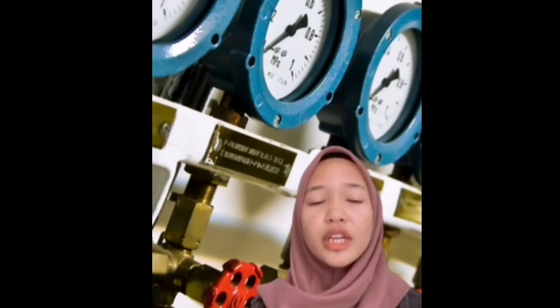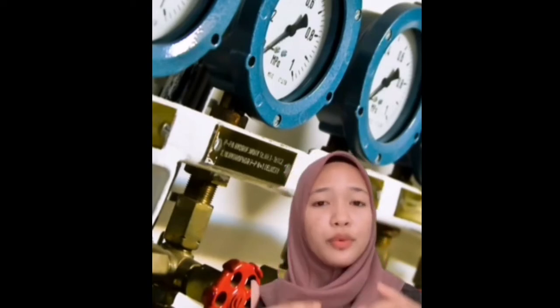Okay, what is feed water treatment? Feed water treatment is a pre-water treatment process to control deposition, eradicate impurities, and prevent corrosion within a boiler system. In a boiler system, water is transformed into steam and expanded by as much as 1,000 times as it passes through steam pipes at rates of 100 km per hour.